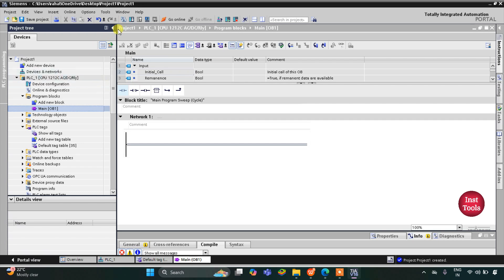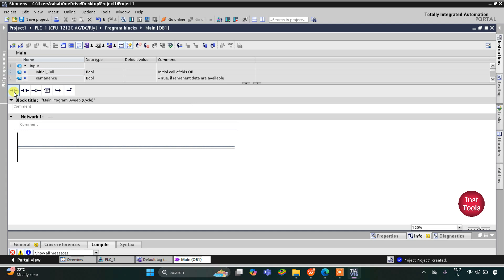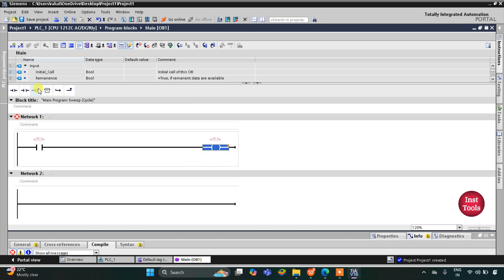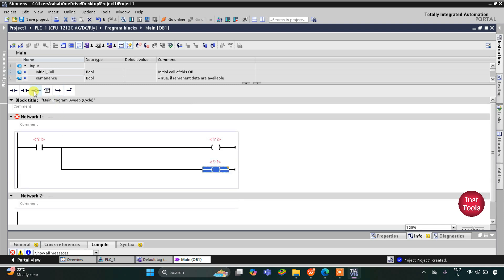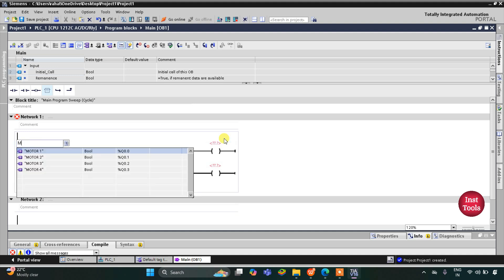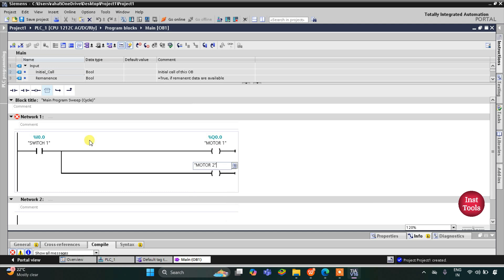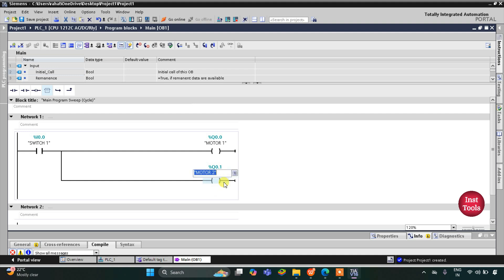Now I will insert a normally open contact for Switch 1, then a coil, and then open a branch and add one more coil. This will be Switch 1, this will be Motor 1, and this will be Motor 2. But the coil for Motor 2 will be a set coil, so I'll click here, then select S from the drop-down list, and press Enter.